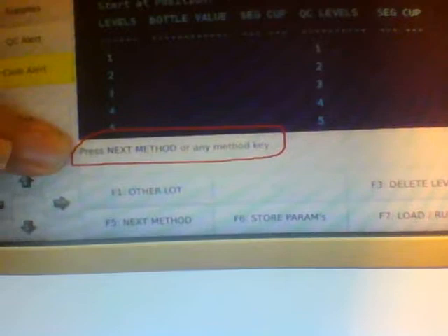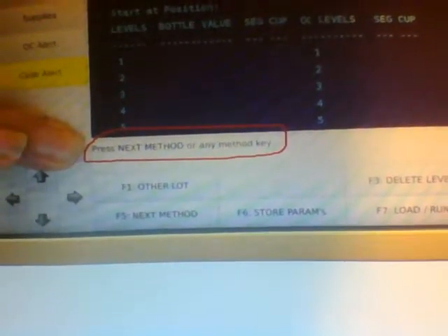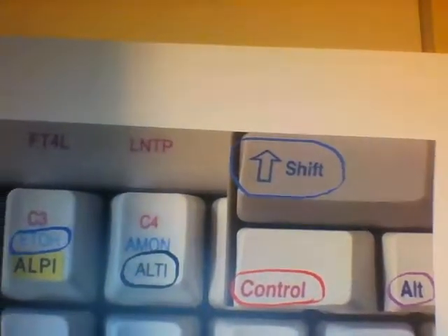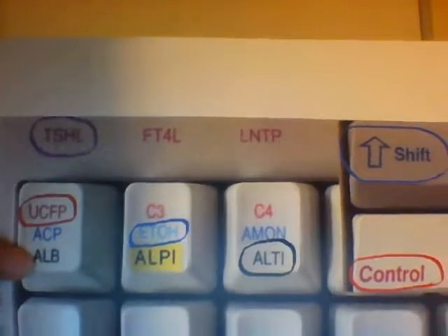Once you push F2, setup and run, you're going to come over here and see an empty place where your calibrations need to be, and it says, press next method or any method key. So you're going to press one of your method keys to get the calibration you want. Now the method keys come in 4 different colors. You're going to have purple, red, blue, and black.